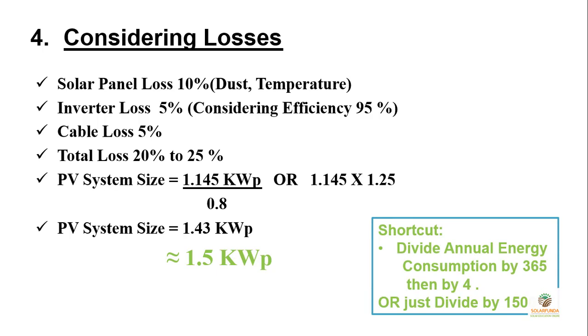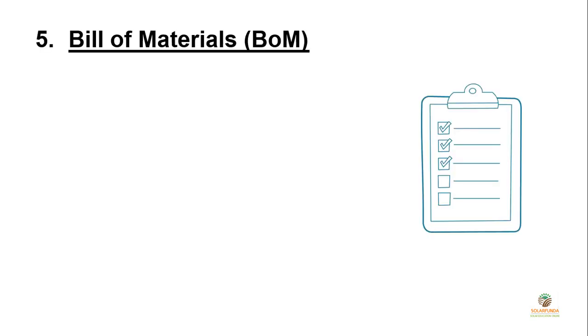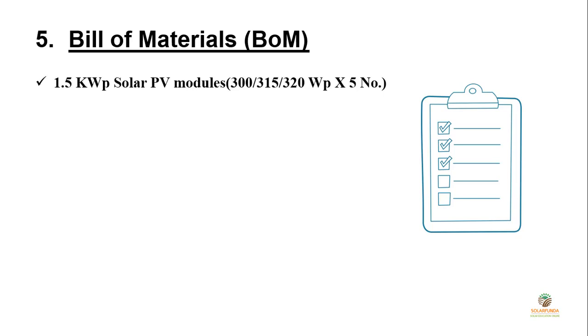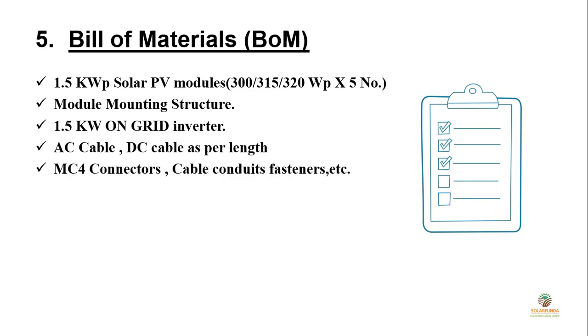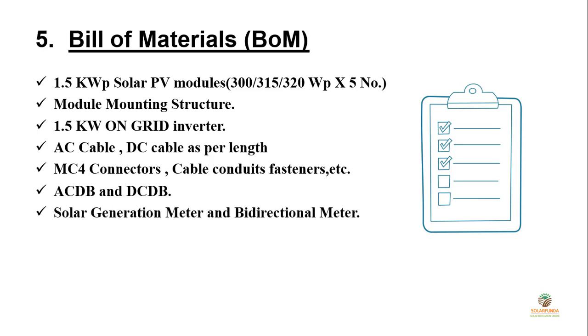A useful shortcut: divide your annual energy consumption by 365, then by 4, or simply divide by 150 to get the system size. For the bill of materials, this includes 1500-watt solar panels — 5 numbers of 300–315 watt panels — a 1.5 kW module mounting structure, a 1.5 kW on-grid inverter, AC and DC cables as required, MC4 connectors, cable conduits, fasteners, switching and protection systems (AC-DB and DC-DB), a solar generation meter, a bi-directional meter, earthing kit, and lightning arrester.